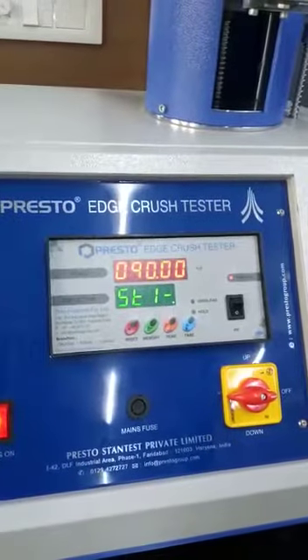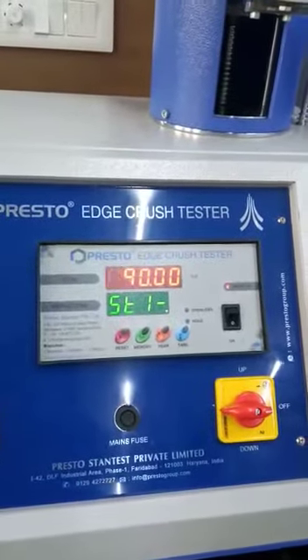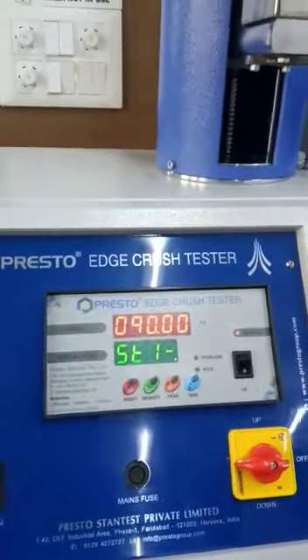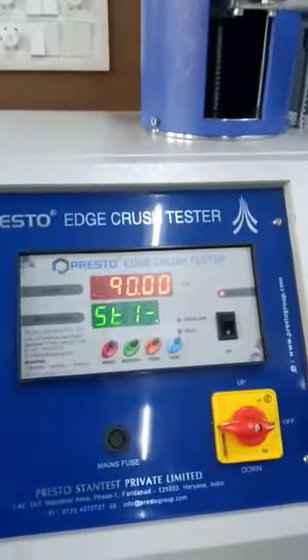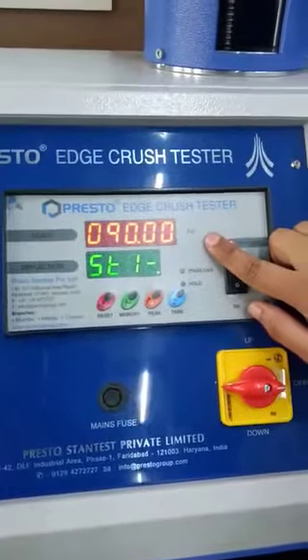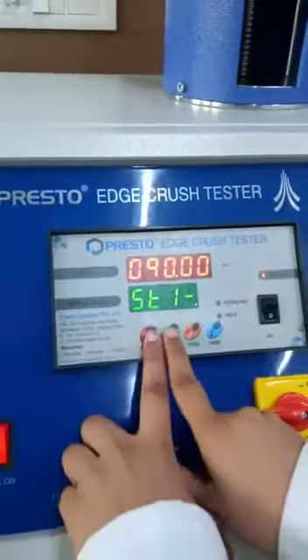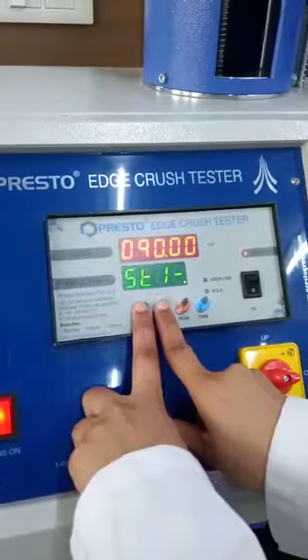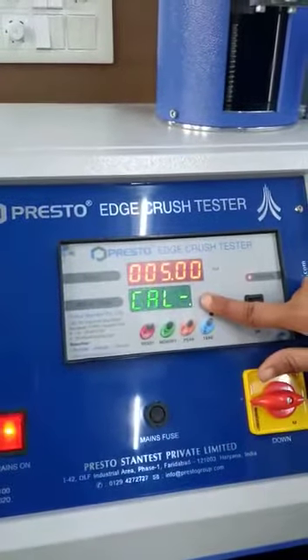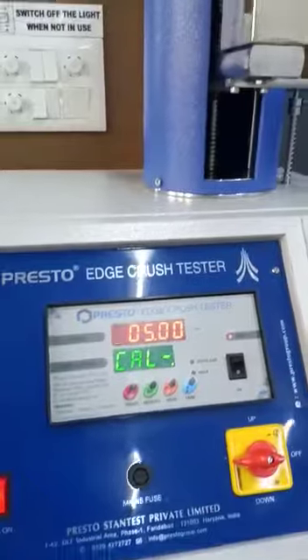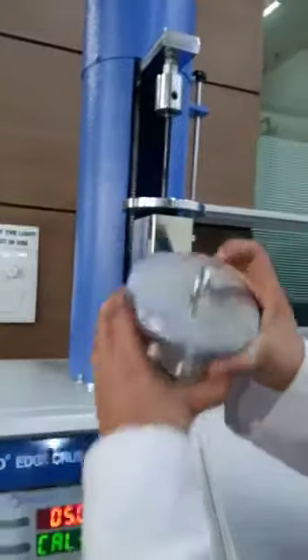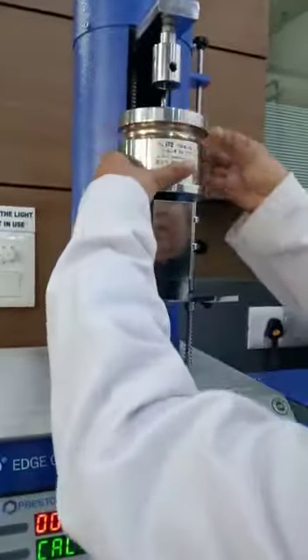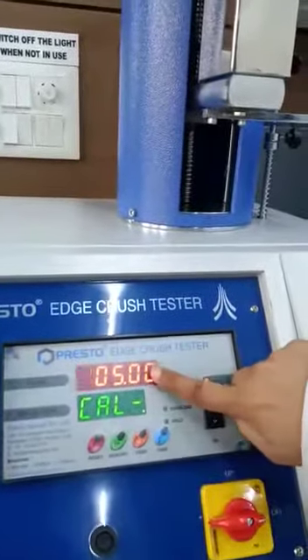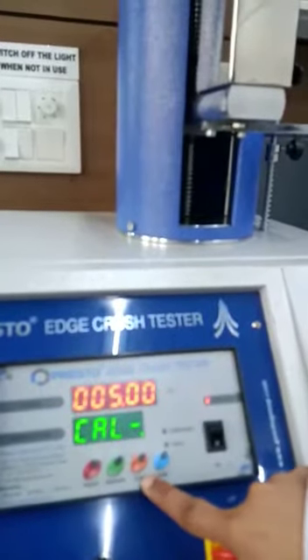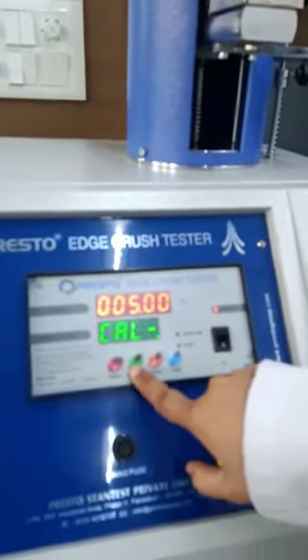So it will show ST1. For a standard machine of edge crush tester, the value of ST1 would be 90.00 kilogram force. Then again press reset and memory together. So it will show cal. Put the known weight on the compression plate and enter the same value here with peak, memory and reset keys.